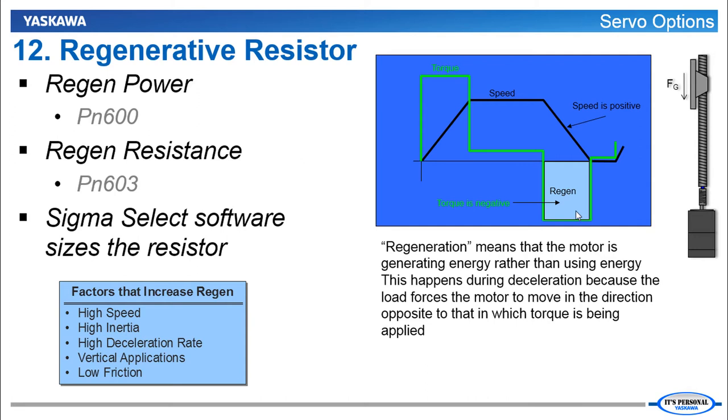Often the amplifier's capacitor can absorb this energy. But in some cases it cannot and you'll need to connect an external regenerative resistor. For which there are two parameters. One is the rated power that should go through that resistor. And the regen resistance. How do you know if you need this? Well our software Sigma Select when you size the servo will tell you how much regen resistance you need. What the resistance should be and the power of that resistor. And of course in that software you can experiment with different speeds, inertias, deceleration rates, angles of inclination for vertical applications and different friction levels to see how that model will affect the predicted regeneration resistor.